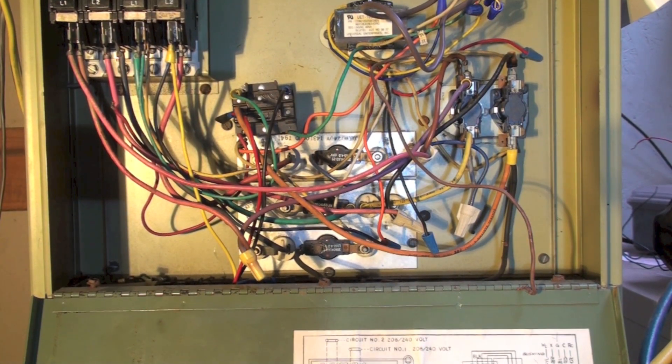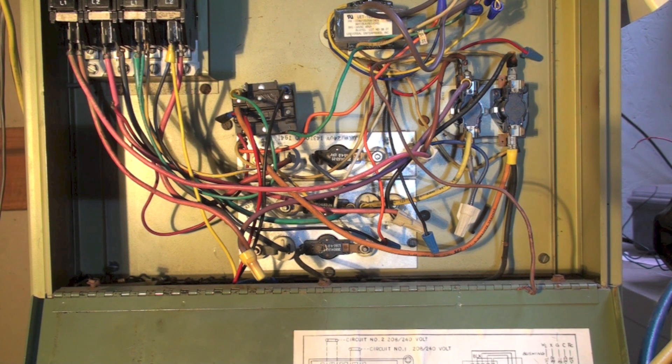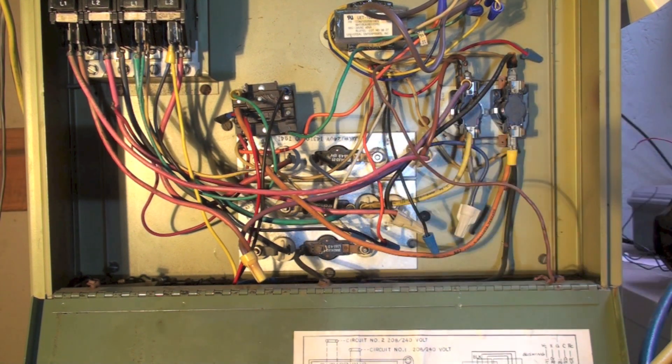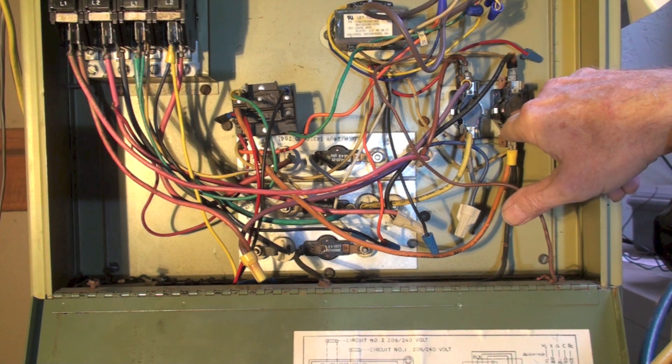Here we have an electric furnace, a fairly standard one. It's 15 kW because it has three elements at 5 kW each. It has a sequencer here, which is a stack type sequencer, and it has a few problems. I'm going to fix them, but mostly I'm going to get rid of this sequencer and put a contactor in there.